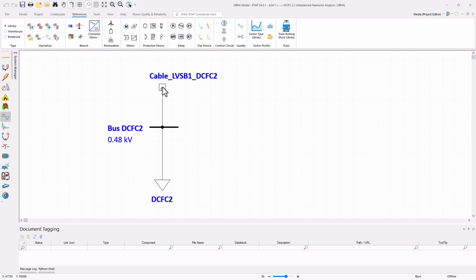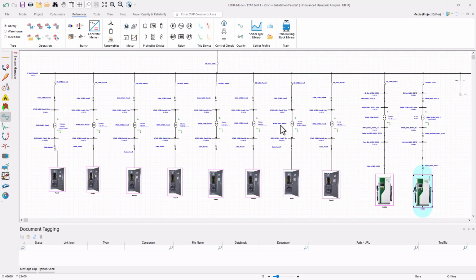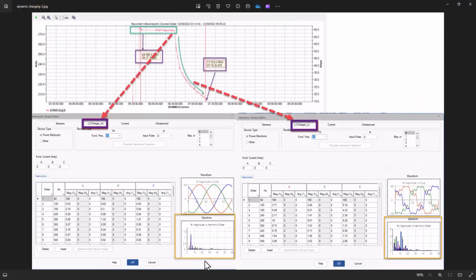While the one-line diagram was being created, we also worked with field-recorded harmonic distortion data for creating harmonic libraries. These libraries were created considering the 95th percentile of the recorded data to use in the modeling of harmonic sources. In case of L3 chargers, the current drawn by the equipment during the charging cycle has a dynamic behavior. The harmonic current injection from this equipment to the grid is also different depending upon the moment in time during the charging period. In order to account for this behavior, two sets of harmonic data have been extracted at two different instances in the charging cycle. One at the beginning of the cycle, where the charger is constantly drawing its rated current, considered to be the highly loaded condition. Another one when the charger current consumption has decreased towards the end of the charging cycle, considered to be the lightly loaded condition.